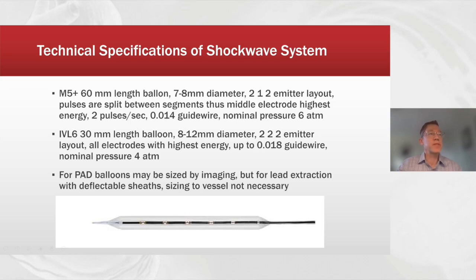The M5 Plus balloon is 60 millimeters in length and 7 to 8 millimeters in diameter, and that's what's been described being used in the literature. Importantly, it has a 2-1-2 emitter layout. And that's important because the pulses are split between those emitters. Thus, the middle electrode has the highest amount of energy, and it goes over an 014 guide wire.